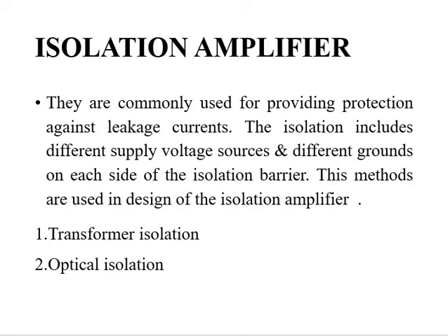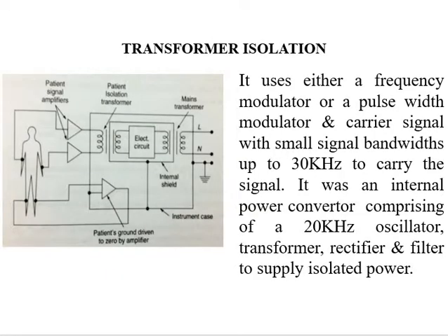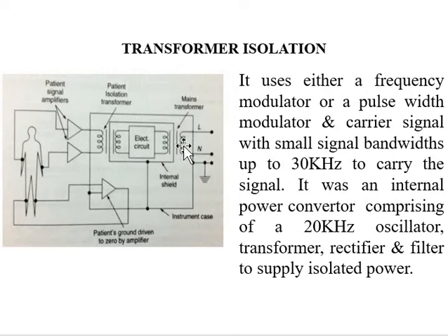Next is optical isolation. We already read about optical isolation in the non-mechanical chopper amplifier, where we had LDR, and instead of LDRs we can replace with photodiodes or phototransistors. The same thing is going to be discussed in this isolation amplifier. Now, for transformer isolation: here is the subject and the signal is taken, amplified using a power amplifier, and fed to the signal conditioning instrument. Inside that we have a transformer — a patient isolation transformer and a mains isolation transformer.